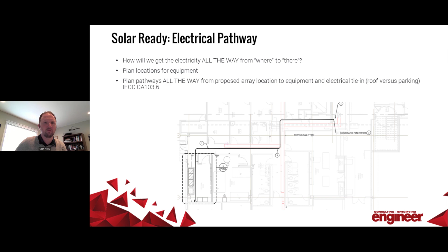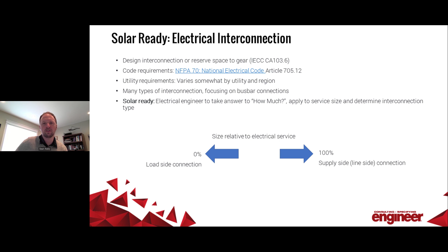From the interconnection standpoint, this is covered in Article 705.12 in the NEC. I could easily spend an hour on this topic, so I'm going to race through it a little bit just to give some general guidance. The smaller the system, the more it will lean towards a load side connection, meaning you're on the load side of your main service disconnect. And the larger sizes are going to go more on the supply side.